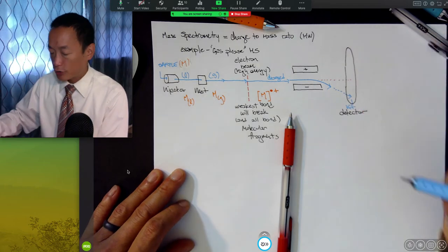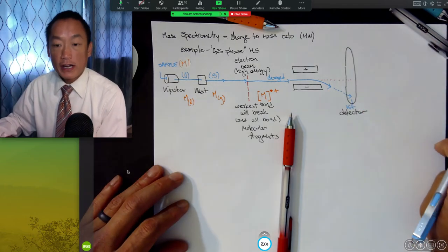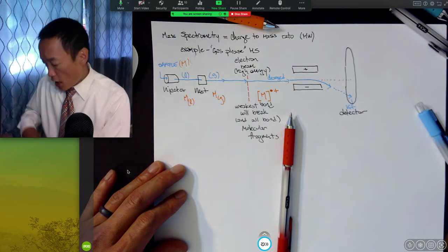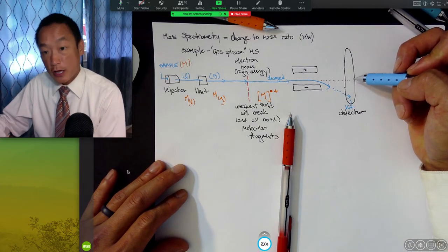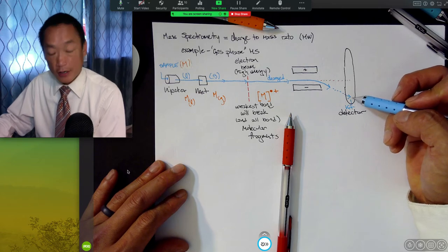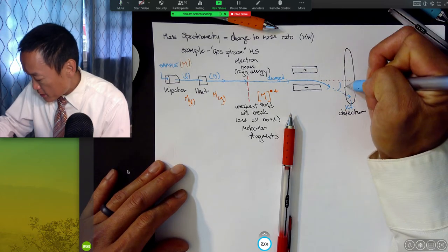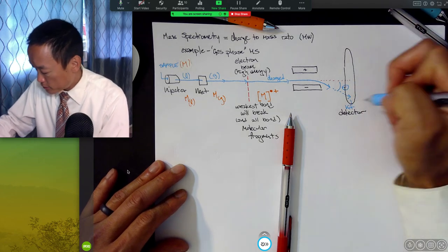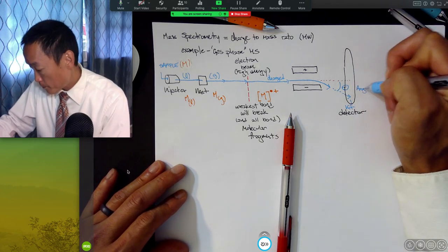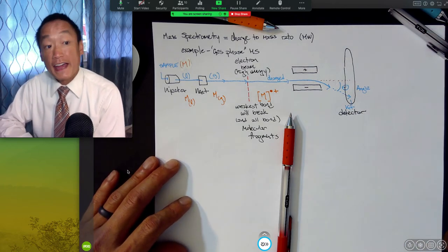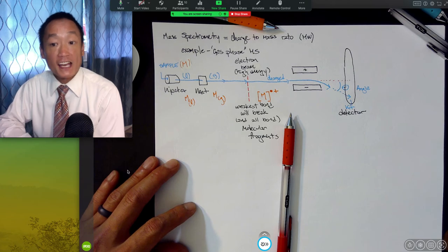It's like Battleship. That's a hit. And when it hits that detector, keep in mind that your instrument now has a reference point of where non-charged molecules should appear and where your molecule appears. This angle right here is what's measured by the instrument. And that angle can then be back calculated.